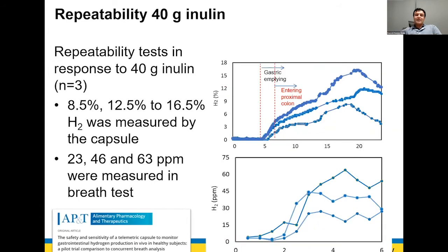And this is the repeatability and association between the breath test and the capsule. So we gave 40 grams of inulin. It's a lot of fermentation happening in these individuals. And we saw that when 23 parts per million of gas could be detected in the exhale of that volunteer, it could produce 8.5% of hydrogen in the gut. And it went up. They were proportional.